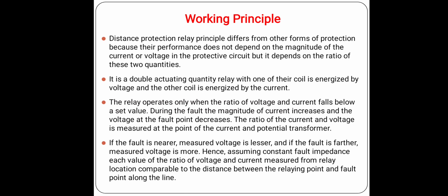Now next is the working principle of the distance protection relay. Distance relays differ in principle from other forms of protection in that their performance is not governed by the magnitude of the current or voltage in the protected circuit, but rather by the ratio of these quantities. That means for a distance protection relay we need to find the ratio of these two quantities, not individually the voltage or the current.